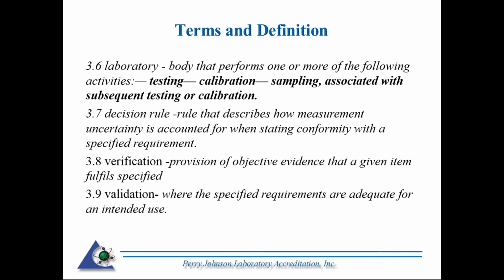The term decision rule. What is a decision rule? Something that's always been required, but now it has to be defined in 2 different places. Basically, in contract review and reporting. So it's always been required that measurement uncertainty has to be taken into account. The decision rule is the rule that describes how measurement uncertainty is accounted for when stating conformity with a specified requirement. We have definitions for verification and validation, and these are separated out and organized very nicely in the 2017 standard.